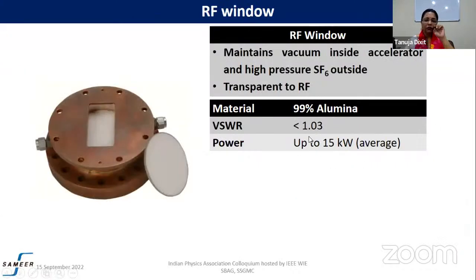So an important part of an accelerator is the RF window. The RF window is used to maintain vacuum inside the accelerator and also to isolate the high pressure SF6 outside, because...